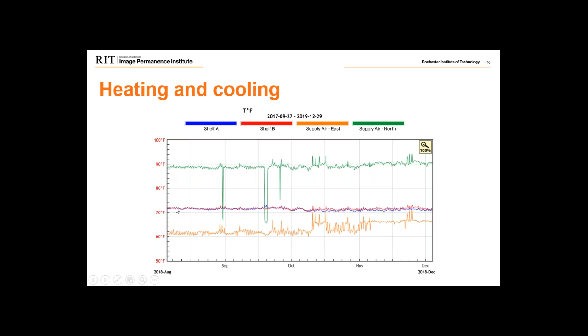Then you paint this picture: we literally have the mechanical system fighting itself, one heating as much as the other is cooling. The response to this was that it turned out to be a broken heater running all the time. Looking back even in August, getting this repaired brought things back in line, and brought the temperatures more in line with what we want.